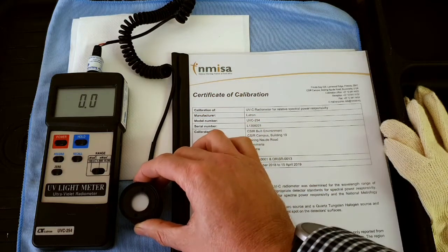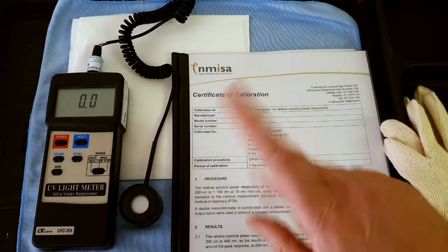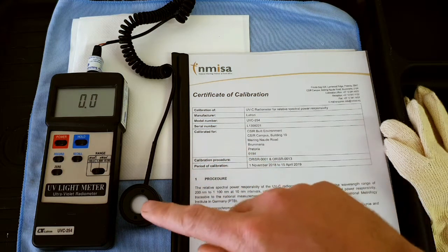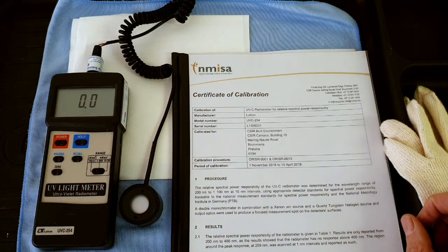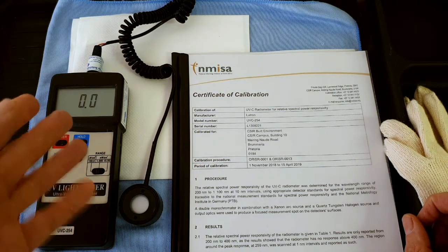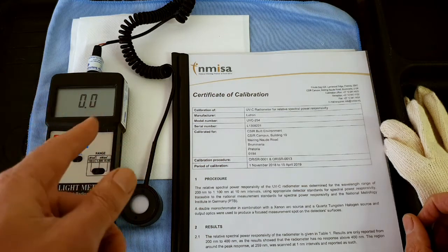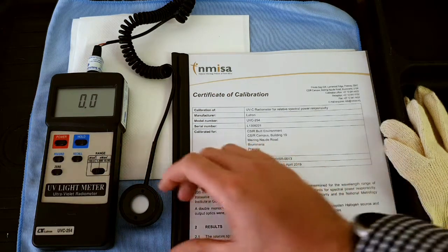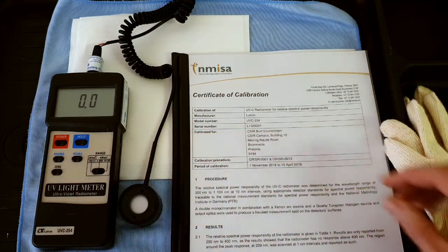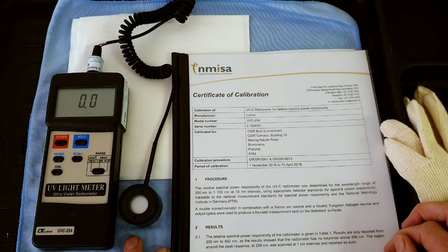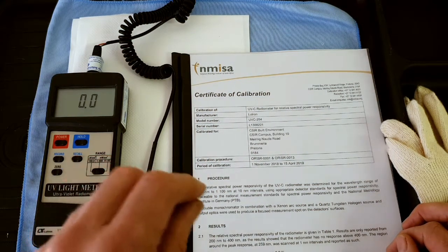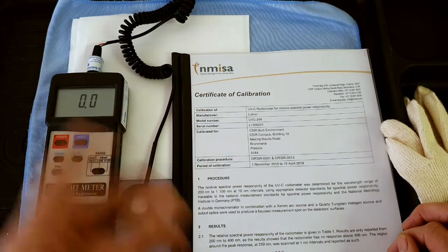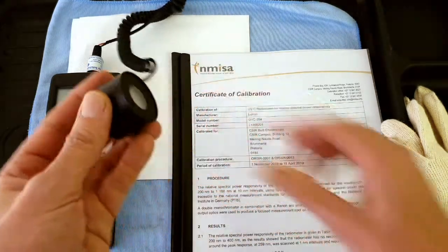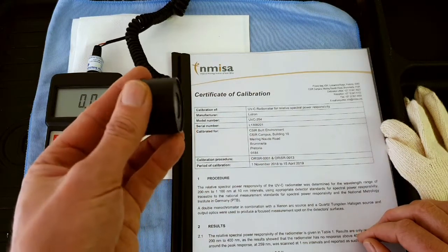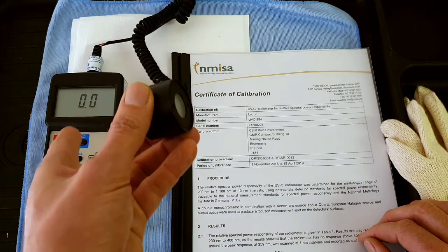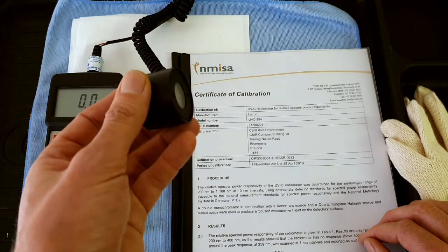And this is not a big issue if you are measuring the power output of a UV light. But if you're doing eye safety measurements, that can be an issue because our limit is quite low. Our limit is only 0.2 microwatts per centimeter squared for general spaces. And that means that is already saturating it a little bit. So what we want to do is take that into account before we do our eye safety measurements. So you'd want to verify that they are not giving you any response. For instance, if I was going to point it into the room, just make sure that we're not receiving any UVB or UVA in the room, if I know the sensor does respond to those, before I do my eye safety measurements.